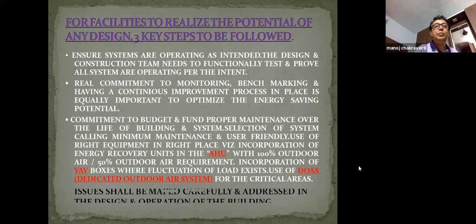How does it decide? Because the software is fed along with the characteristics curve of the chiller. That characteristics curve shows at a certain percentage of loading, the chiller gives maximum efficiency. With that logic, the software will select whether 2 or 3 chillers will run, because this will finally give the energy saving.